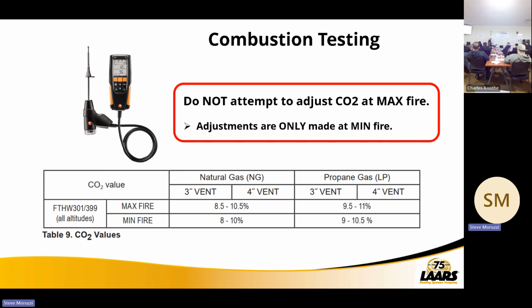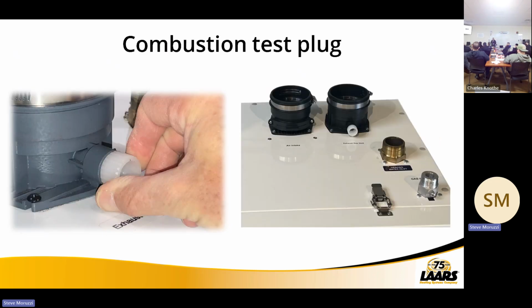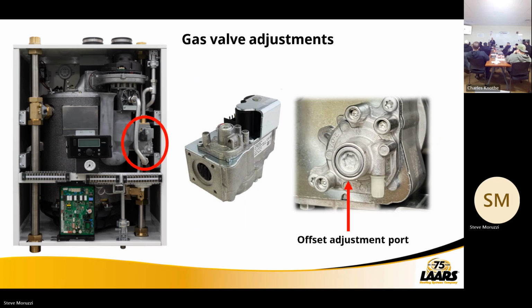So you're going to adjust it now. You're going to compensate the high fire with the low fire setting. So I'm going to go clockwise, increase that. Keep my analyzer in, be patient with your analyzer, 90 seconds. Before, I would wait before I even start to do anything else. And then go back to my dip switch, shut dip switch 7 off, fix on, go back to full fire, and now I should be back below my 10.5. So compensate on low fire for high fire adjustment.